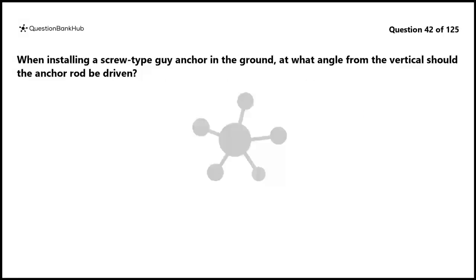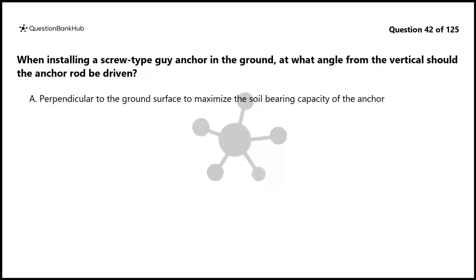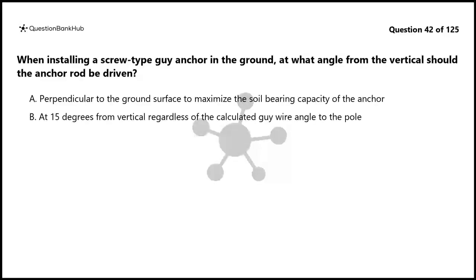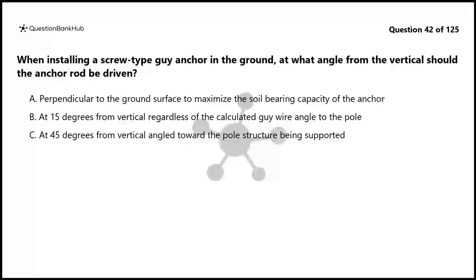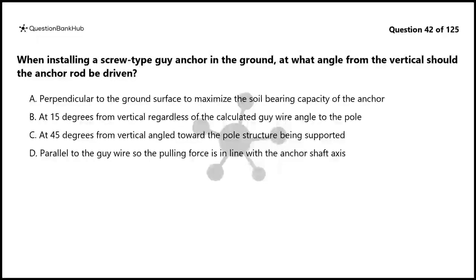Question 42. When installing a screw-type guy anchor in the ground, at what angle from the vertical should the anchor rod be driven? A. Perpendicular to the ground surface to maximize the soil-bearing capacity of the anchor. B. At 15 degrees from vertical regardless of the calculated guy wire angle to the pole. C. At 45 degrees from vertical angled toward the pole structure being supported. D. Parallel to the guy wire so the pulling force is in line with the anchor shaft axis.